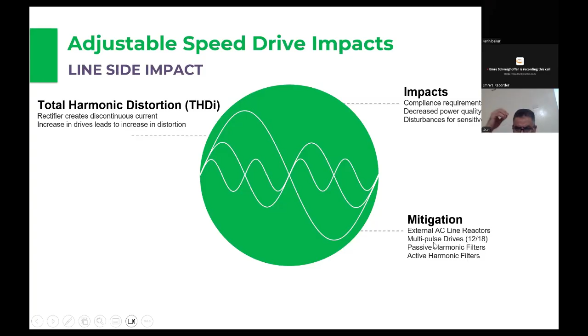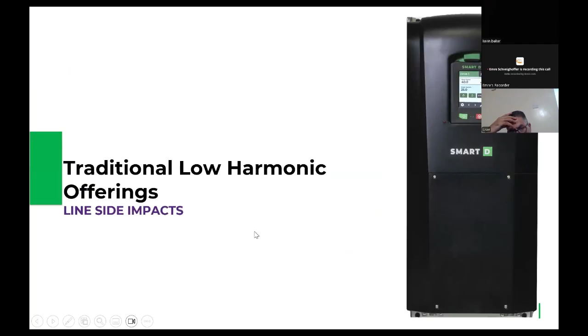And then how do you mitigate that on the line side? Well, there's good, better, best. There's reactors. You can go with multi-pulse drives. You can go with passive harmonic filters, active harmonic filters. So let's continue on with the line side impacts.